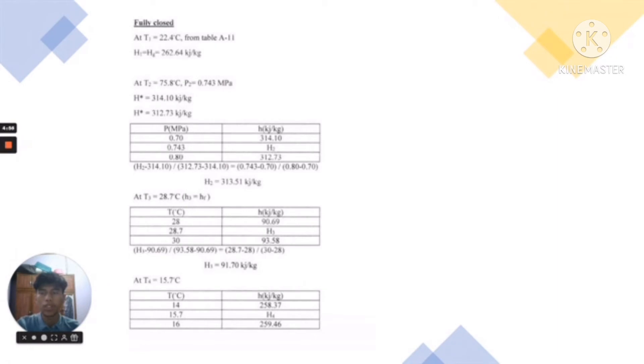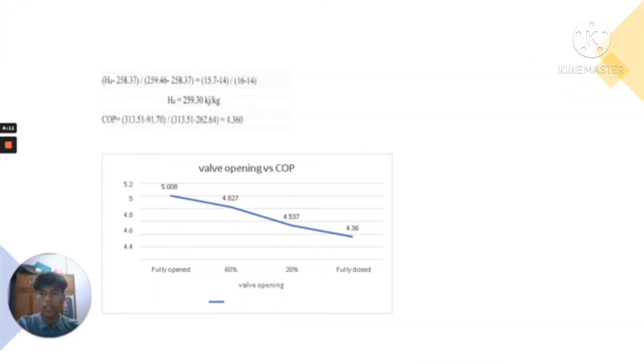For the fully closed valve, at T1 equal to 22.4°C, H1 is 262.64 kJ/kg. At T2 equal to 75.8°C with pressure equal to 0.743 MPa, H2 is 313.51 kJ/kg. At T3 equal to 28.7°C, H3 is 91.70 kJ/kg. At T4 equal to 15.7°C, H4 is 259.30 kJ/kg. The coefficient of performance is 4.360.